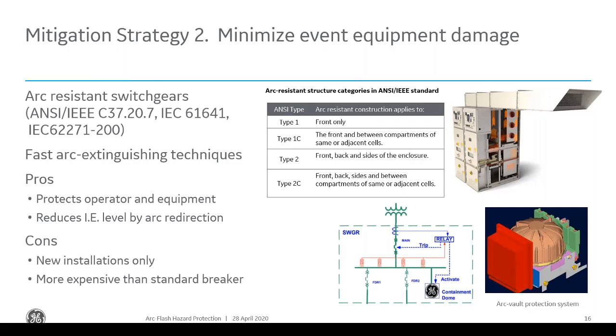There are also some extinguishing techniques to deal with arc flash once it occurs. The concept is based on detection and removal of an arcing fault before it escalates into an arc blast or elevated arc hazard risks, such as high temperatures, which, as I mentioned, is the most severe. Basically, with Type 2C, you have arc flash resistance from all corners of the switchgear: front, back, sides, and between the compartments. And for Type 1, you would only have it in the front, so you can only approach from the front of the switchgear.